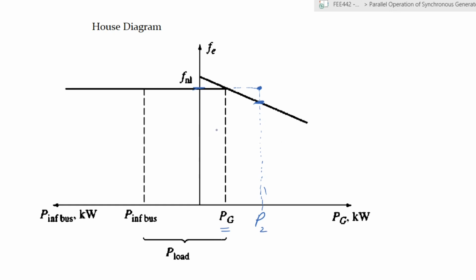You want this power at this frequency F of the bus bar. Let's call it FE. Your no load frequency is here. So you change the governor set points to match that value. So you have set point 2, and this is the original set point. What this tells you is that if you want to supply an infinite bus bar, whatever amount of power you need to supply, you have to adjust your governor to meet the frequency that is required.